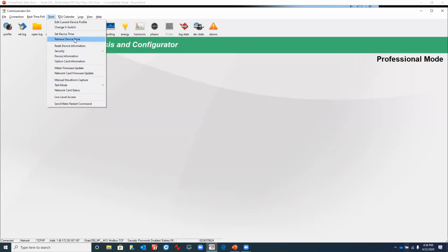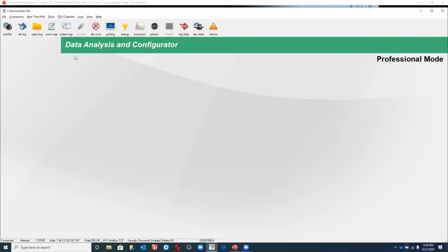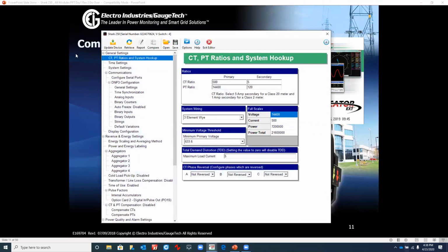The current device profile is probably the most important area that we'll want to discuss, and we'll go right into that discussion. So we'll retrieve the meter programming settings from the device, and initially once you connect, you will see all the parameters that we need to set up for the meter, which are CT, PT compensation, time settings, system settings, communications. You can configure the serial communication settings, the DNP settings, and general settings on the DNP. So everything that falls under DNP is all the settings that, once you enable it, are going to be impacted by the changes that you make in the setting.